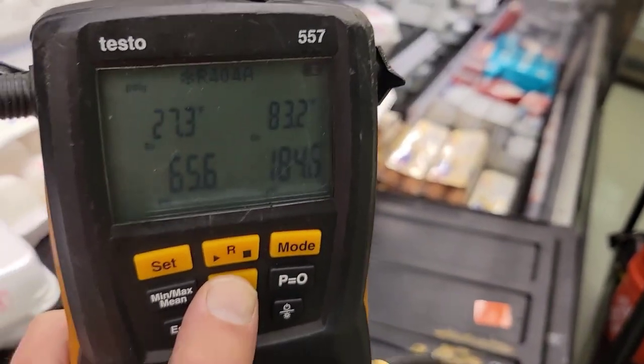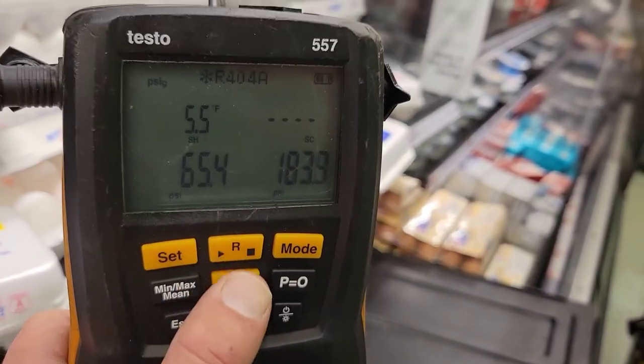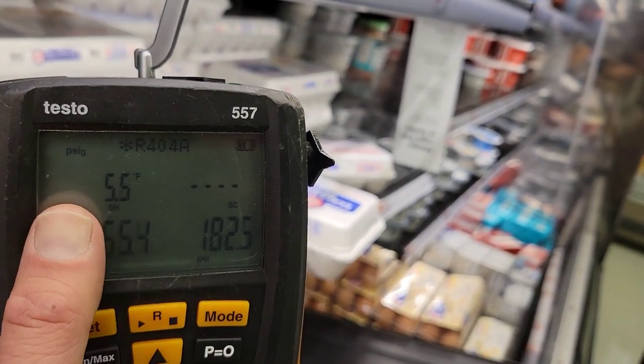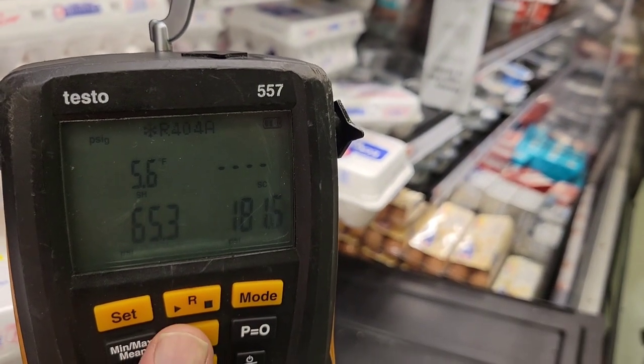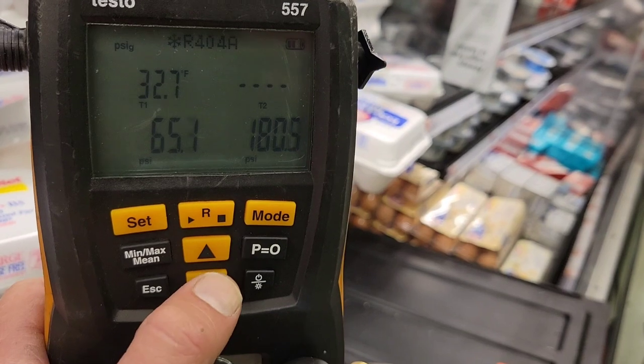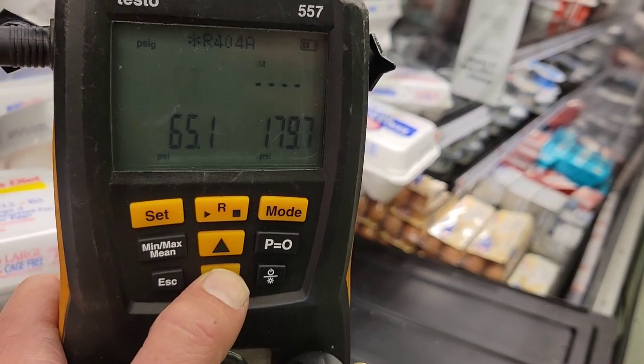So my gauges do superheat. It's gonna take a couple minutes to really get in accurately, but right now it's saying about 5.6 degrees superheat. So even the superheat seems to be okay right now, but we're just gonna let it run for a couple minutes.